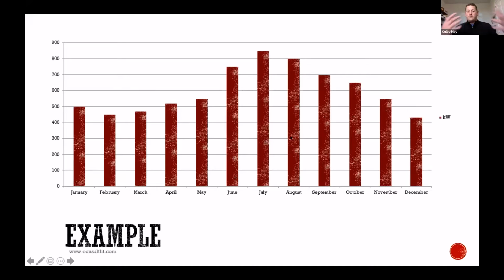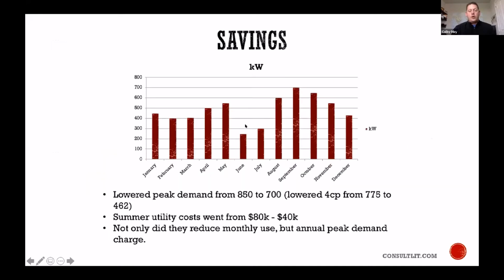We found a no-cost solution. It's a pretty complex issue, but a simple no-cost practice saved that school $40,000, simply by changing the runtime hours, the outside air dampers, and more. So again, benchmarking tells us a story, and we're able to use what we find to investigate in a more equipped way.